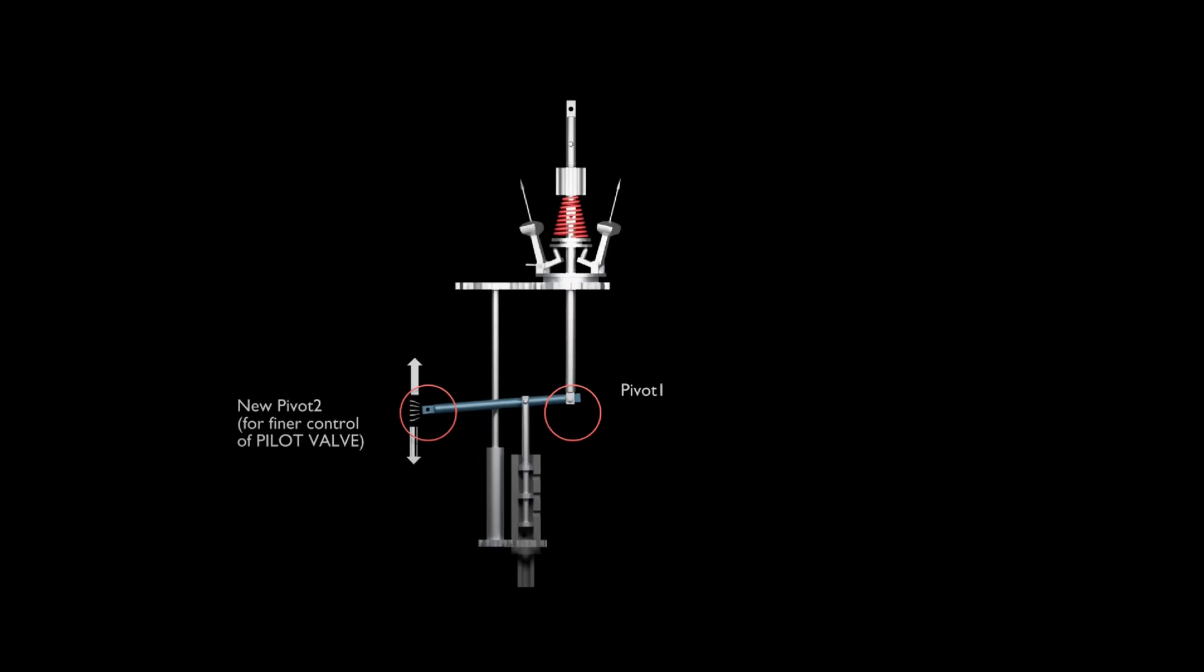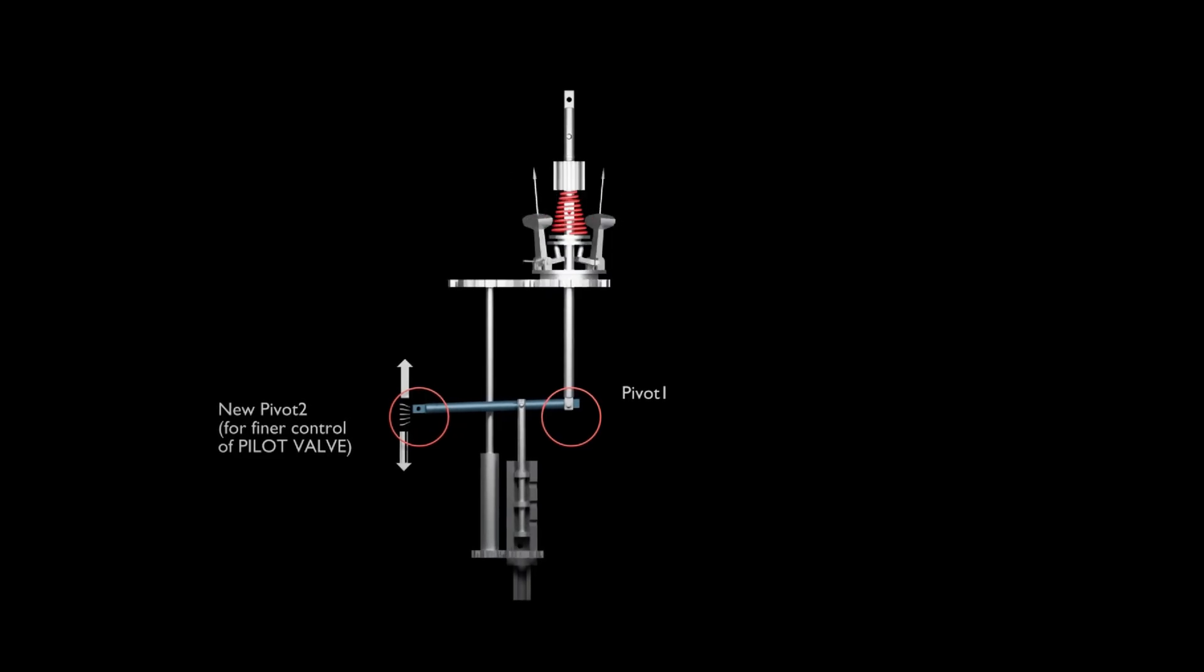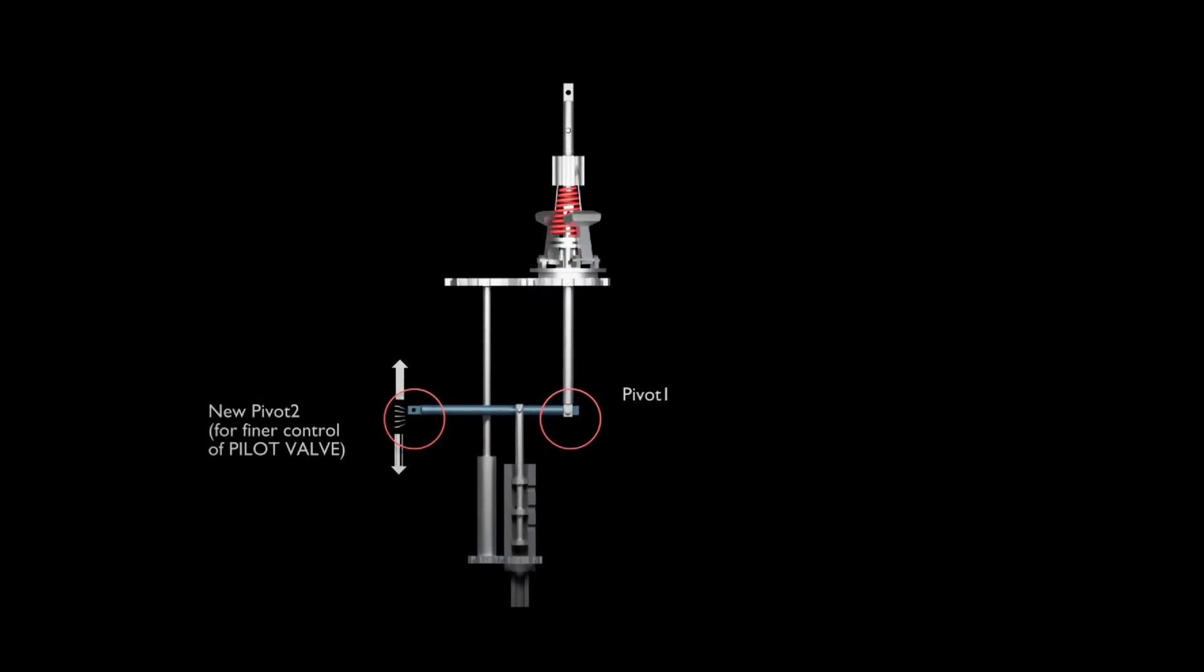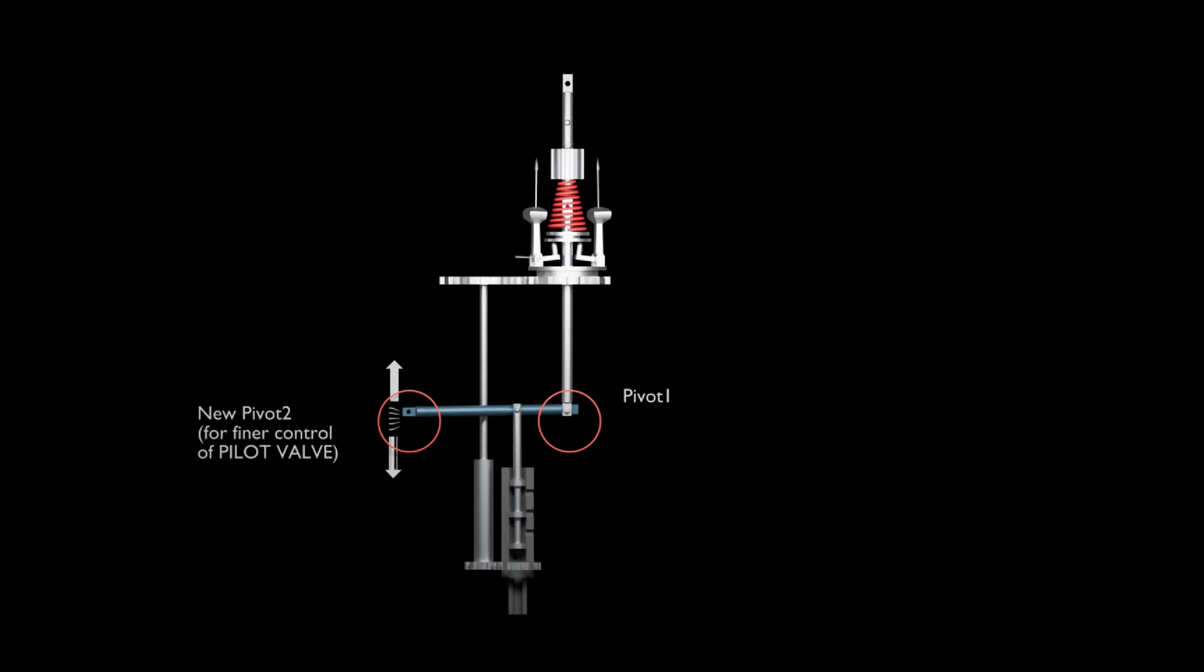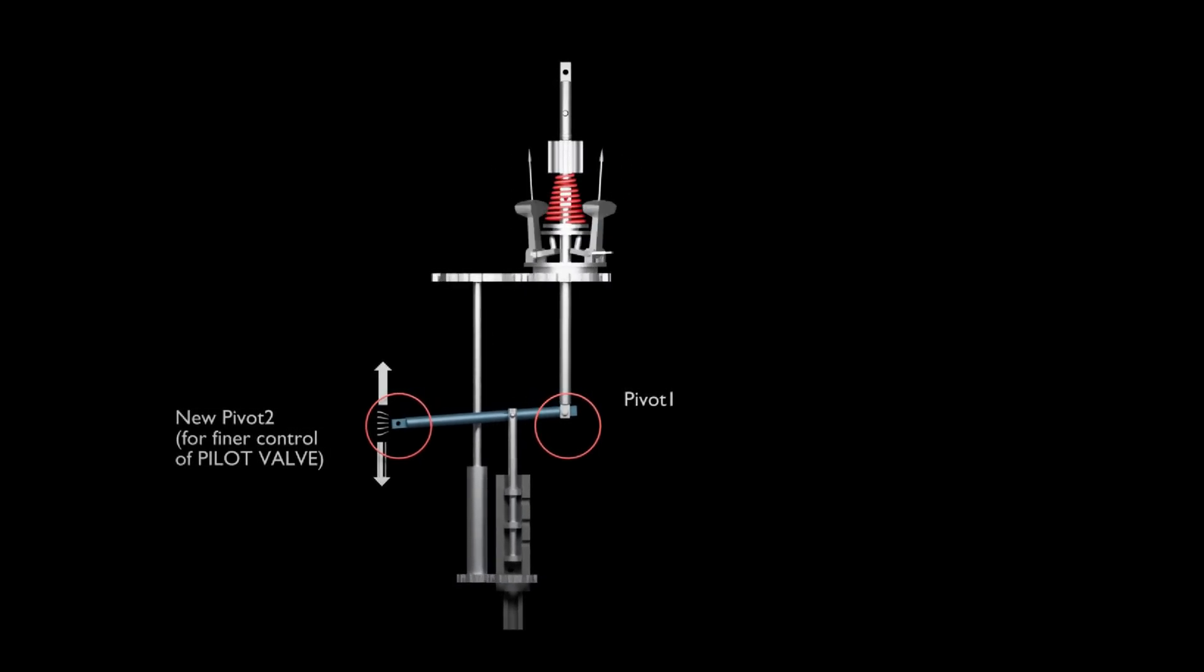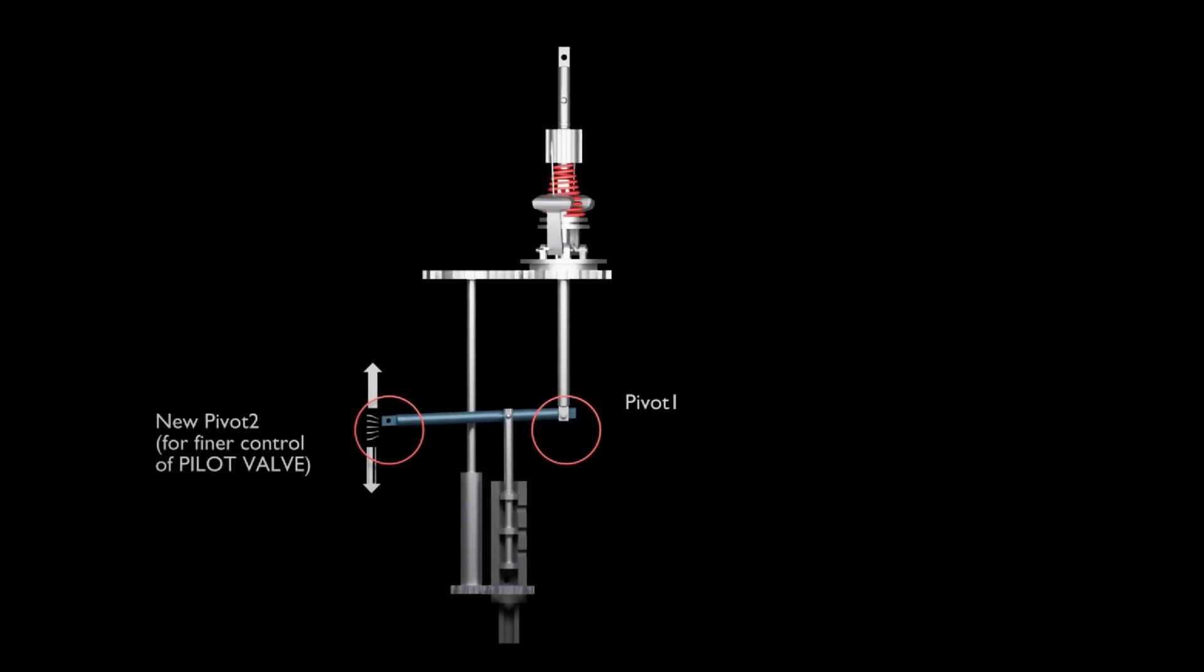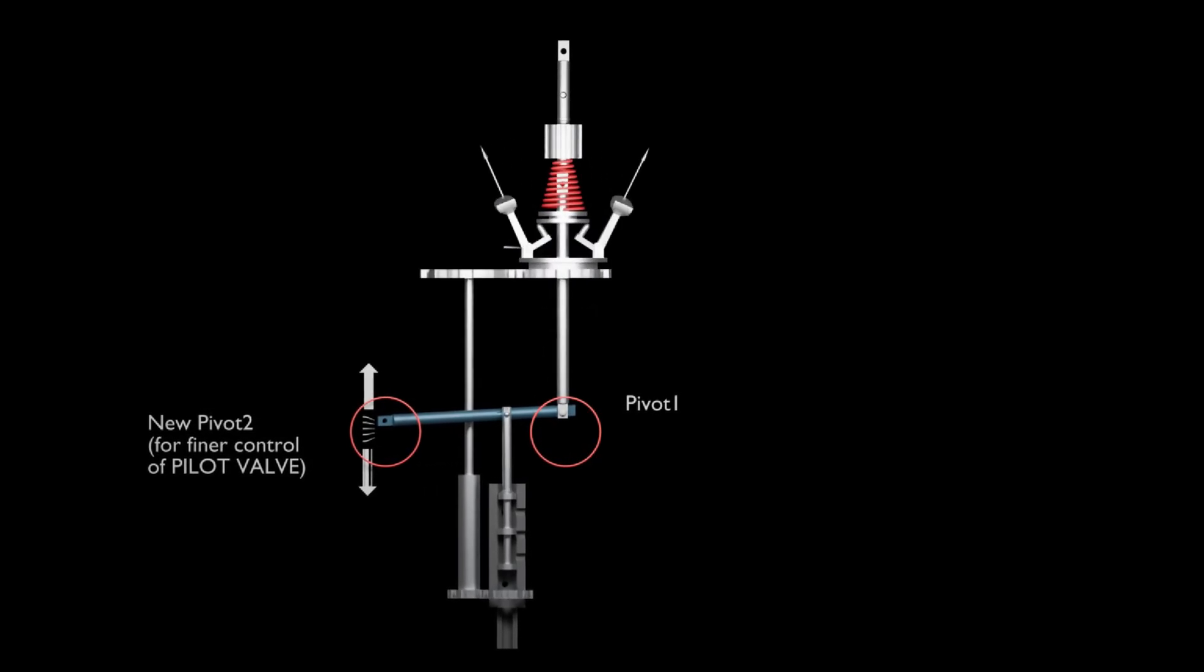So this new feedback will work in opposite to pilot valve movement due to flyweight's positioning. Its objective is to keep the pilot valve closer to cover port 2 earlier than could be possible by flyweight feedback alone. Two, this extra traveling input must vanish after the lapse of the time lag, as if there was no such input that ever existed.